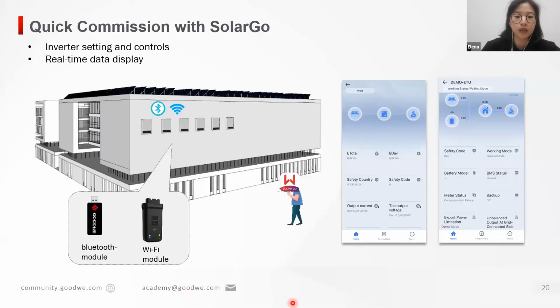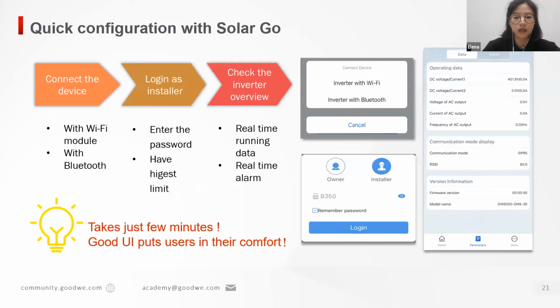For some inverters with screen, you can do the setting directly via the screen, but also we provide the SolarGo app for both on-grid and storage inverters to do the local commissioning. Via the communication modules like Bluetooth module, Wi-Fi module, the installer can connect to the app. Then they can see some basic real-time data for the inverter like E-day, E-total in the homepage, and then they can do some setting. The connection and the commissioning of the inverter takes just a few minutes.